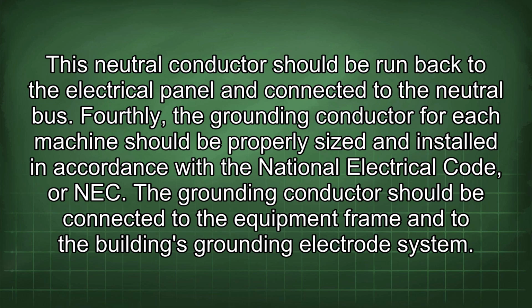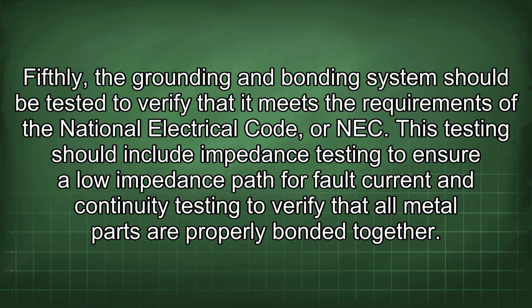Fourthly, the grounding conductor for each machine should be properly sized and installed in accordance with the National Electrical Code, or NEC. The grounding conductor should be connected to the equipment frame and to the building's grounding electrode system. Fifthly, the grounding and bonding system should be tested to verify that it meets the requirements of the National Electrical Code, or NEC. This testing should include impedance testing to ensure a low impedance path for fault current and continuity testing to verify that all metal parts are properly bonded together.